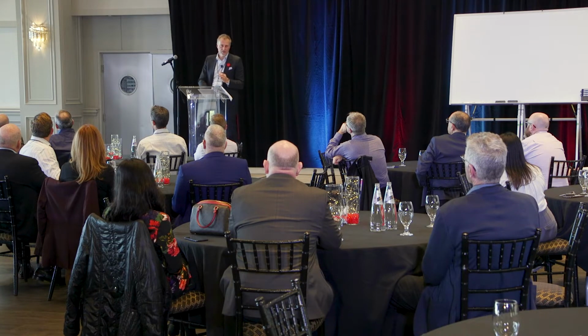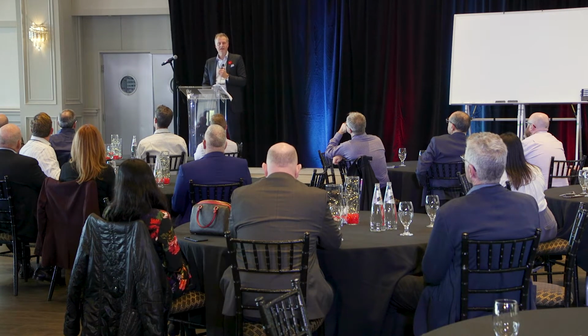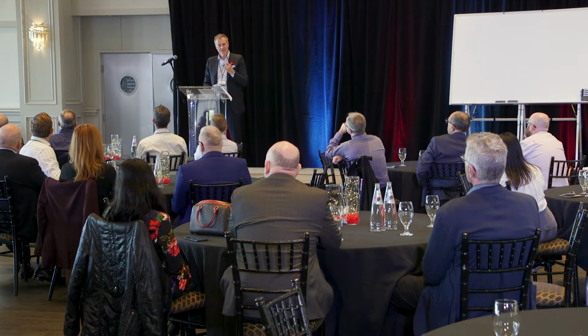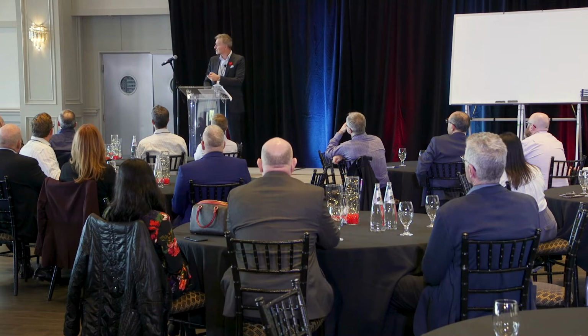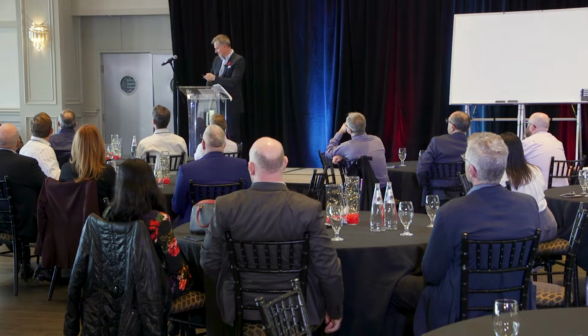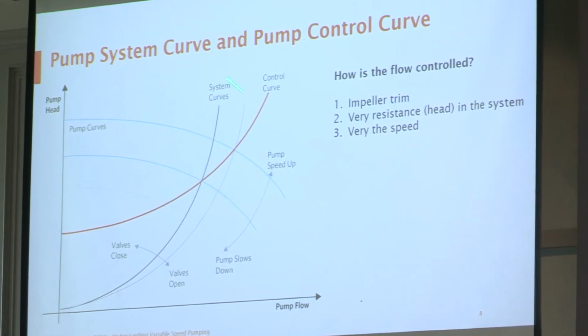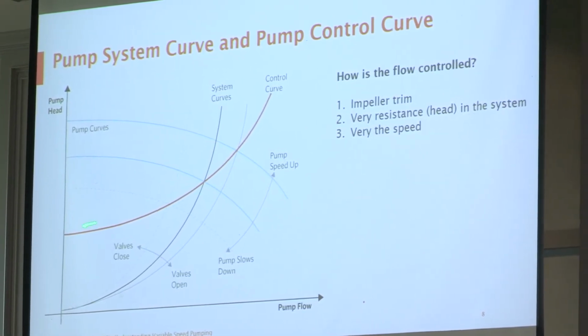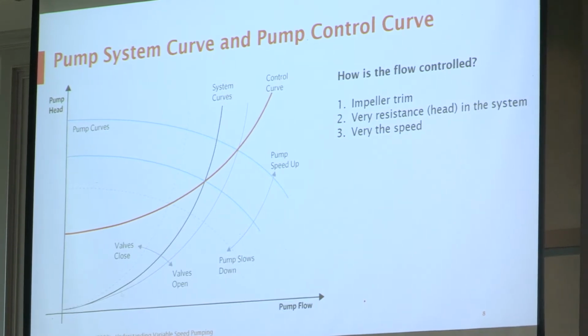The control curve is the line that a pump is operating on in a variable speed application. And the way the control curve is determined is based on your DP sensor location. And what they're saying then is that in our systems, when we go to 50%, we're operating here, we should be using 30% of the power. Challenge is, in a traditional system, to get that control curve.